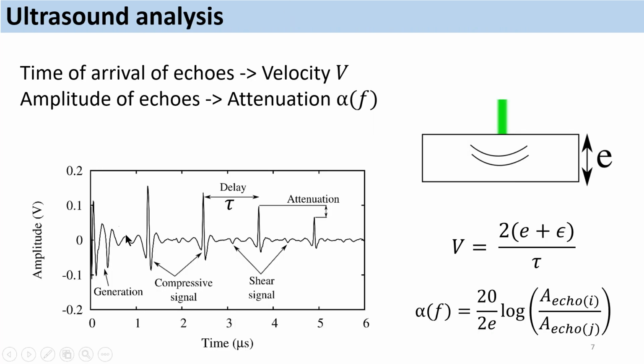So let's look a little bit deeper into the waveform itself. This is the signal that we measure using the Lumet system. This signal consists of several echoes, as I've said before, and mainly two parameters are extracted from this waveform. The first parameter is called the velocity, so it's the speed of sound, and it can be deduced by doing the ratio between the propagation distance, which is often twice the thickness of the sample, divided by the delay, and the delay is simply the time between two successive echoes.